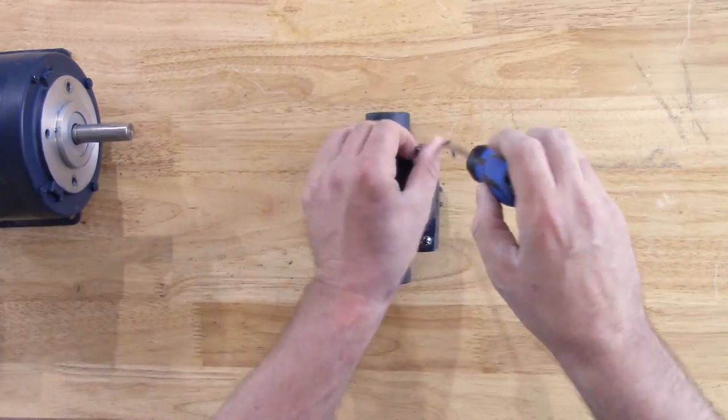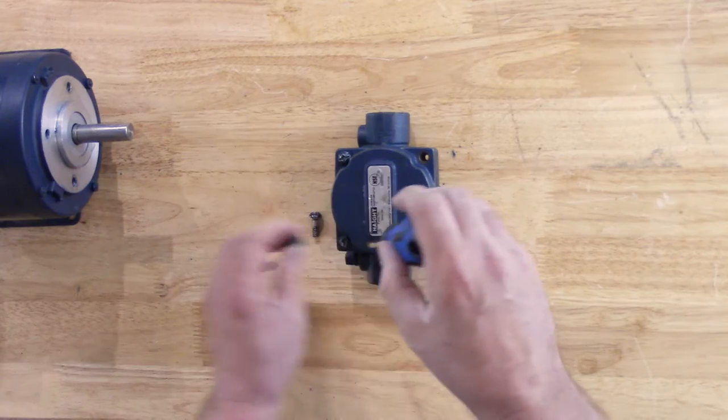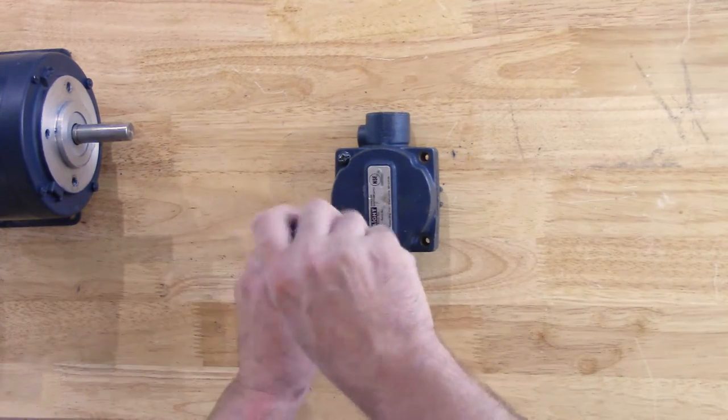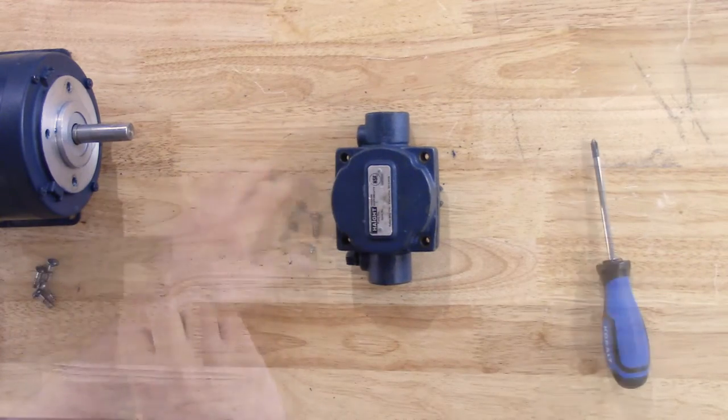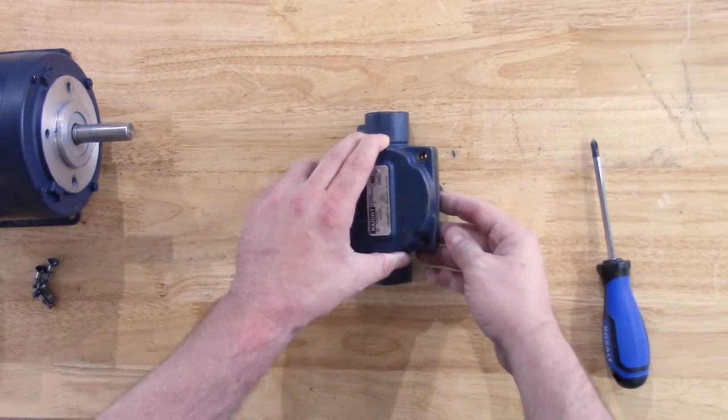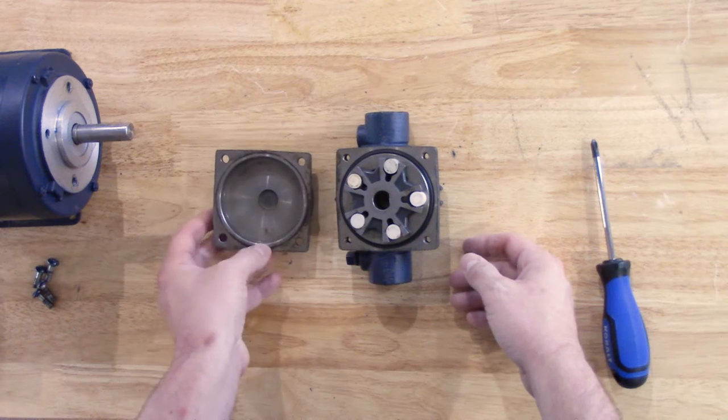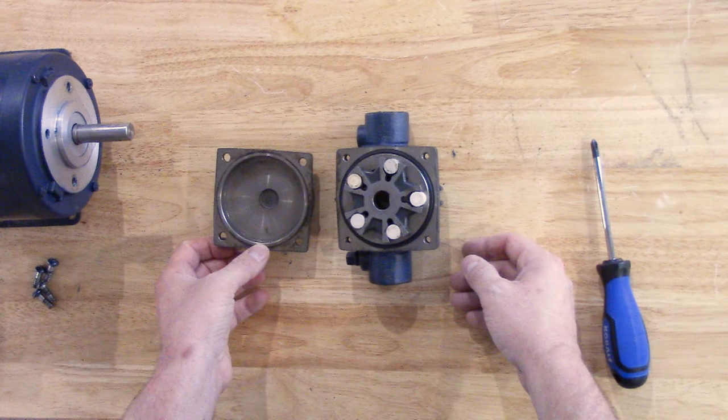After we have the inside of the pump housing clean, we can remove our four bolts that hold our pump cap in place. Now that we have our pump cap bolts removed, we can separate our cap. At this time, we want to make sure that we inspect our pump O-ring as well for any nicks or flat spotting, as this is a good time to replace this O-ring.